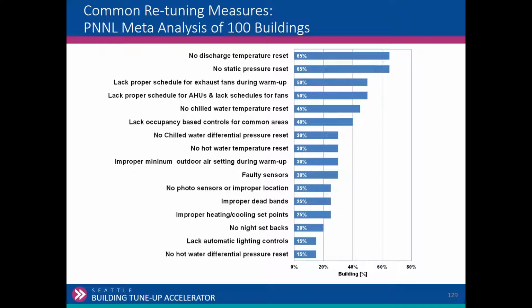Proper schedule for exhaust fans during warm-up. During the warm-up cycle, before there's occupancy, you're bringing the building up to temperature. Do the exhaust fans need to be on? Generally not. Now, if there's occupancy and you've got bathroom exhaust and that type of thing, then you probably do want to run those exhaust fans. But generally at 4 o'clock in the morning when you're initiating your warm-up cycle, or 5 o'clock, you don't need to run your exhaust fans. How would you verify whether or not the exhaust fans were running? You could trend it. If you have a start-stop trend, fan on, fan off, you could trend it. Any other ways? A motor logger on the exhaust fan, so I can find out if the exhaust fan is coming on at 4 o'clock in the morning or 7 o'clock when it's occupied. Any other way?